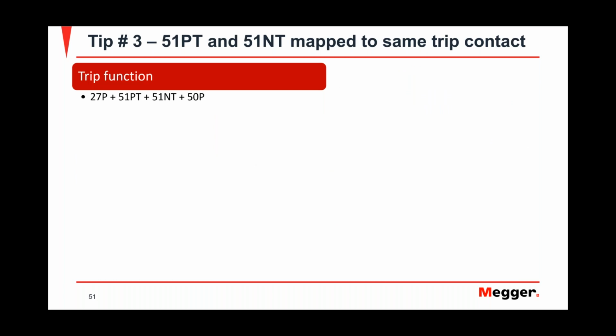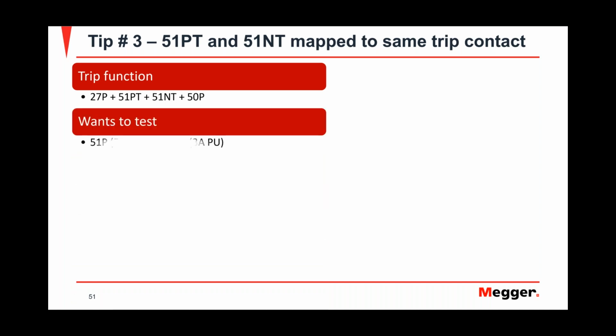Next thing is, now with microprocessor relays, you get these trip functions. And sometimes it can be overwhelming trying to understand what's going on. So I want to show you 3 different ways to see the same logic equation. So let's say your trip or an output contact is programmed with this function: it's a 27P, 51PT, 51NT, and your 50P. And on here, I'm sorry, I take it back. What I meant to say is I have another example with that.